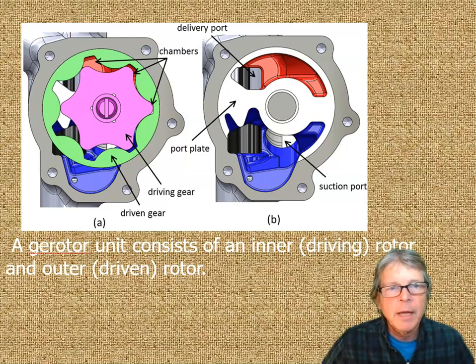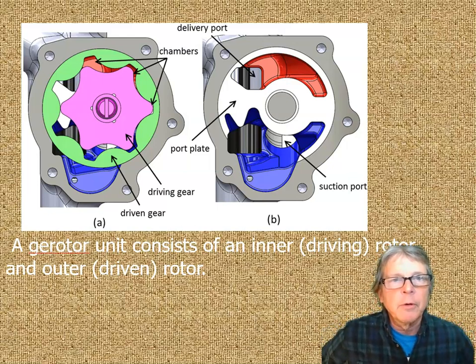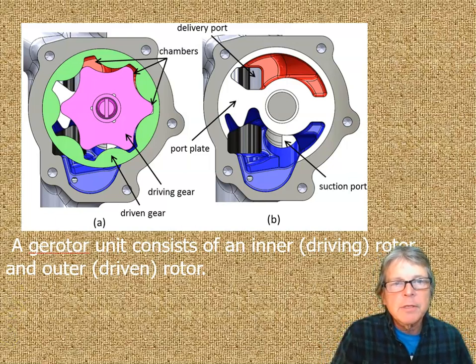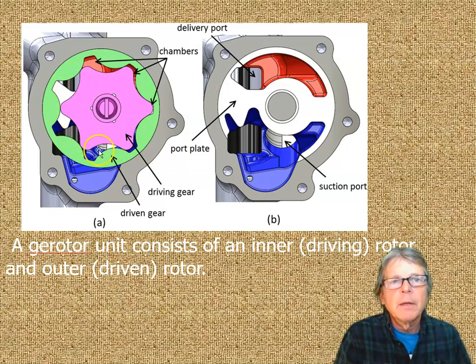Here you can see we have the inner driving rotor and the outer driven rotor is what they talk about here. This is the driven gear here. You can see it says right here, hey, I'm just reading it. And this drives, and this guy here rotates. All right, so we have, and then if you take these out, this is the backside. So you see, this is where we suck, where fluid sucks in. It sucks in as it gets bigger, as the openings get bigger, and it's squeezed out where the openings get smaller. So we pull it in, it gets bigger, bigger, bigger, bigger, and then we start squeezing it out, and we transfer it from here to here. That is a gerotor.